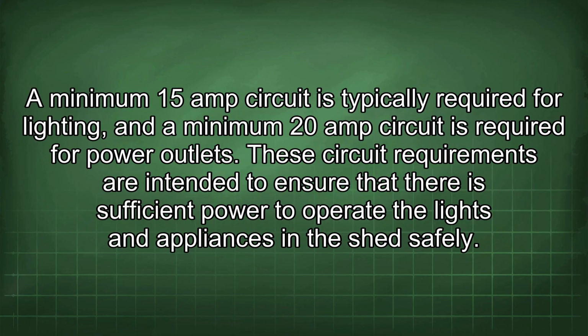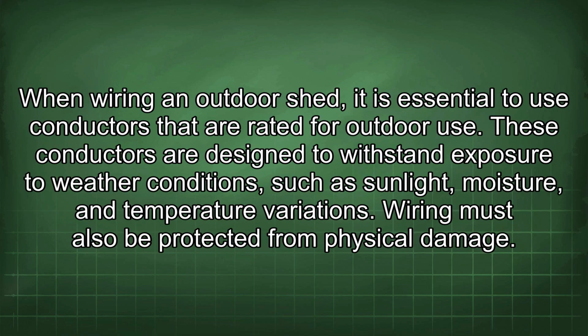A minimum 15 amp circuit is typically required for lighting, and a minimum 20 amp circuit is required for power outlets. These circuit requirements are intended to ensure that there is sufficient power to operate the lights and appliances in the shed safely. When wiring an outdoor shed, it is essential to use conductors that are rated for outdoor use. These conductors are designed to withstand exposure to weather conditions such as sunlight, moisture, and temperature variations. Wiring must also be protected from physical damage.